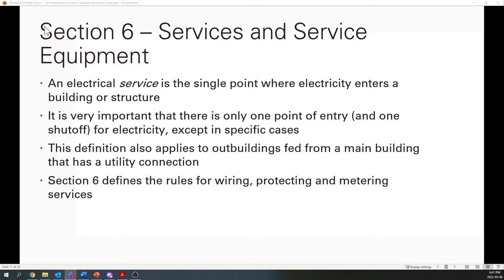In general, though, you can only have one electrical service. This definition also applies to outbuildings fed from a main building that has a utility connection. I volunteer for a facility that has a large number of outbuildings, where one building has the utility connection, and then that building feeds like 40 other buildings. The point of electricity entry to each of those 40 buildings is still a service as defined by the code, even though it's not a utility connection.